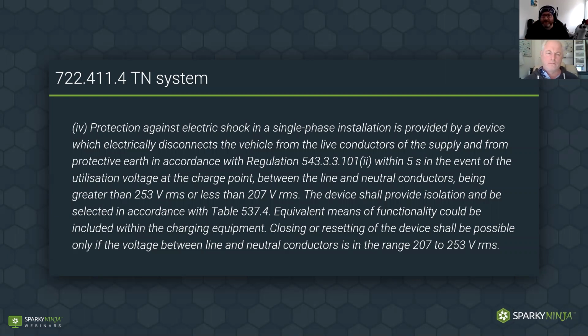A couple of problems with this, and I couldn't find a good way to display this in the time frame that I had. I'm going to recommend you look at a couple of manufacturers because they've done a lot of effort to kind of explain the issue with this regulation. We're relying on voltage monitoring to take place between line and neutral and assuming that if there's a loss in the PEN conductor, that would then take that installation's voltage below or outside of that area, and it will then just identify that and go off. Here's the problem. This is for single phase installations only.